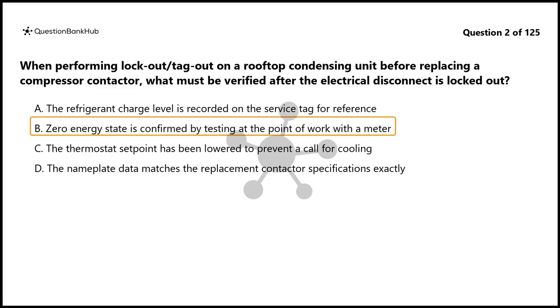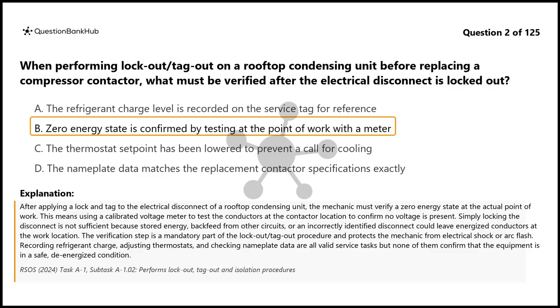The correct answer is B. After applying a lock and tag to the electrical disconnect of a rooftop condensing unit, the mechanic must verify a zero energy state at the actual point of work. This means using a calibrated voltage meter to test the conductors at the contactor location to confirm no voltage is present. Simply locking the disconnect is not sufficient because stored energy, backfeed from other circuits, or an incorrectly identified disconnect could leave energized conductors at the work location. The verification step is a mandatory part of the lockout-tagout procedure and protects the mechanic from electrical shock or arc flash. Recording refrigerant charge, adjusting thermostats, and checking nameplate data are all valid service tasks, but none of them confirm that the equipment is in a safe, de-energized condition.